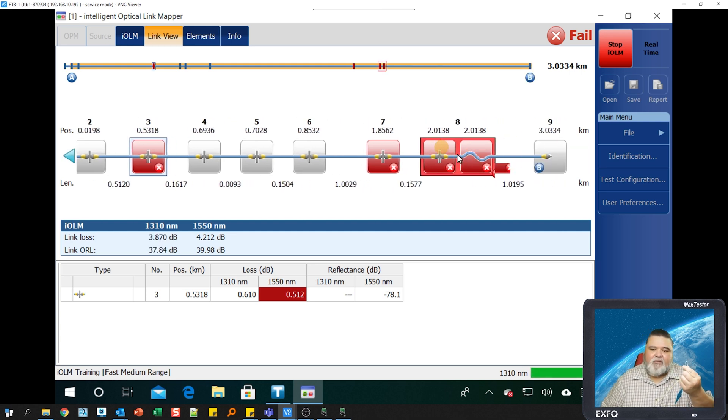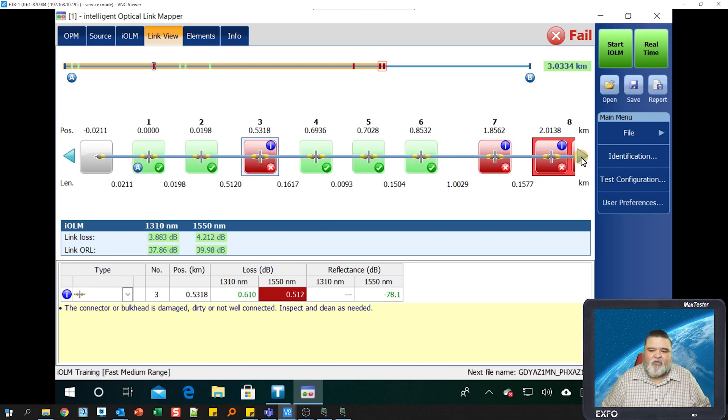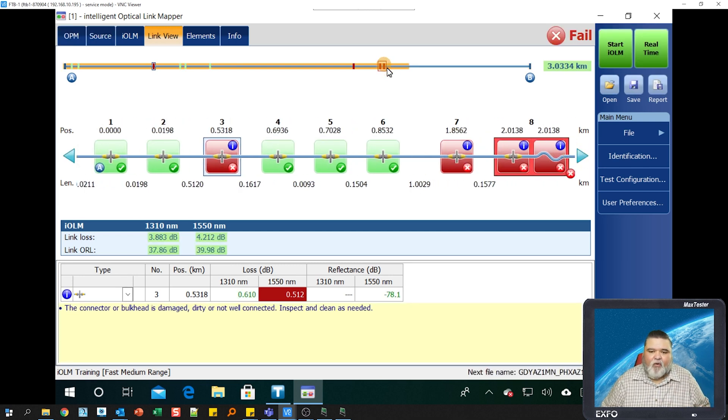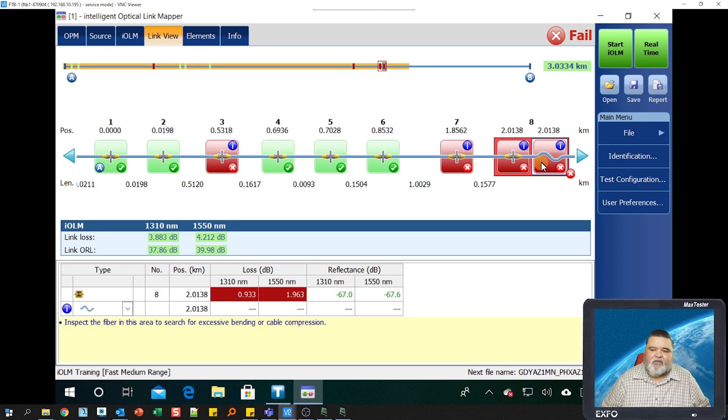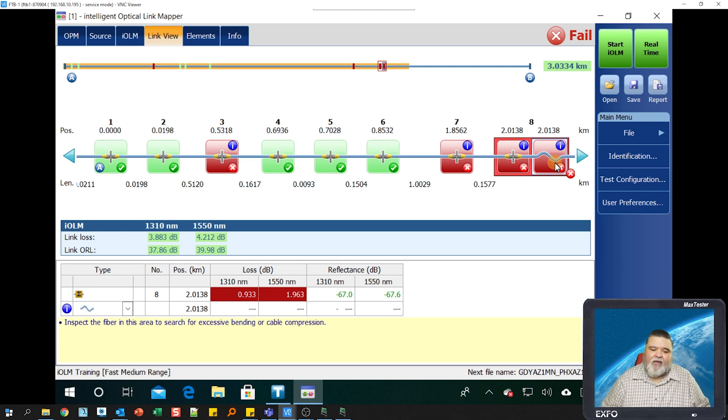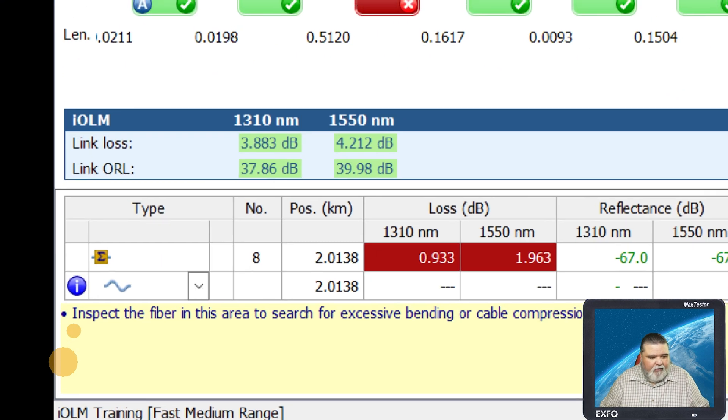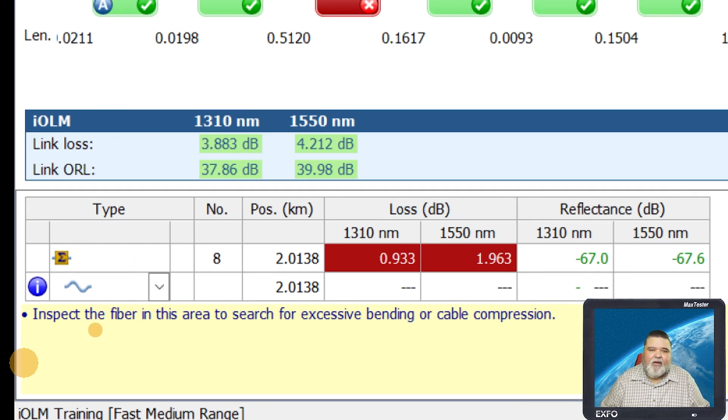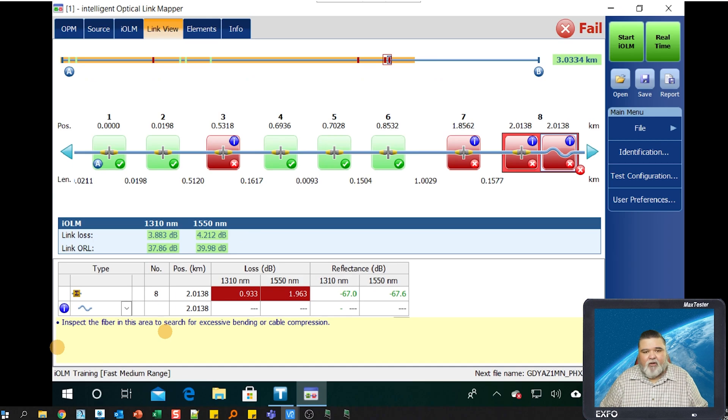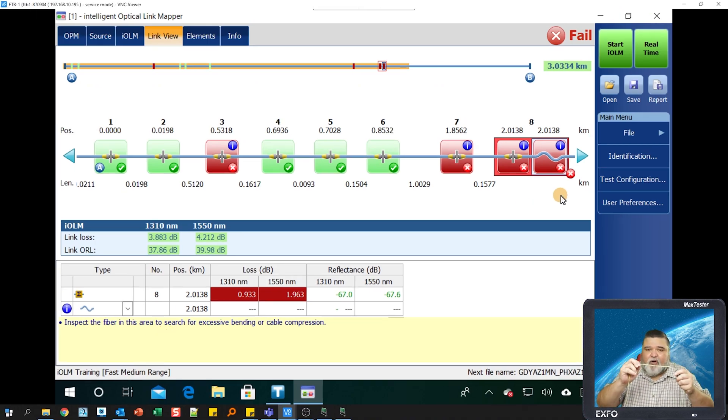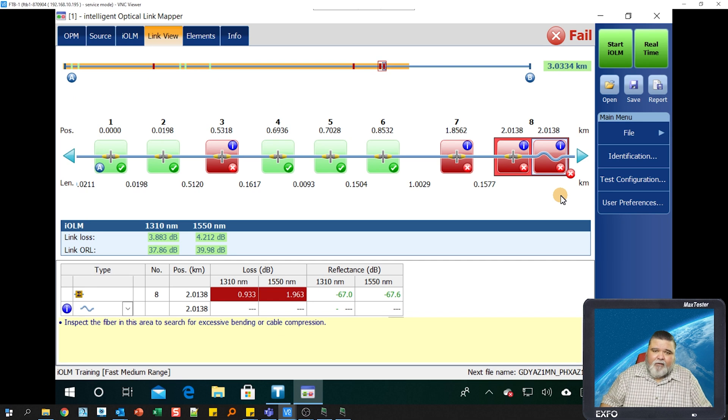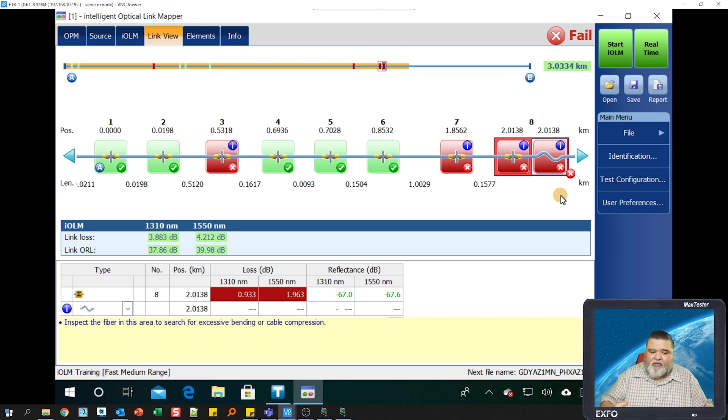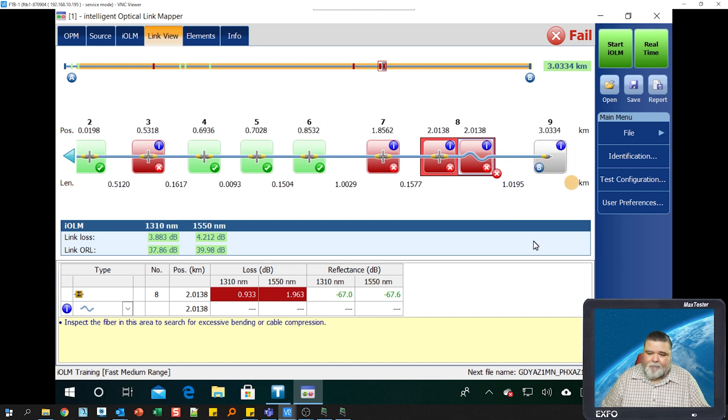We should see an indication somewhere here pretty soon of a pinch. I'm just scrolling back and forth as it's testing the different wavelengths. You'll see right there, we have a new icon. Now that we're done, I can see at two kilometers, we have a connector with reflection. This is an APC connector, and then we have a pinch in the fiber. If you read what it says down here at the bottom, inspect the fiber in this area to search for excessive bending or cable compression. That basically tells you got a pinch in the fiber, some sort of cable compression. If I remove that and retest, it'll be a lot better.